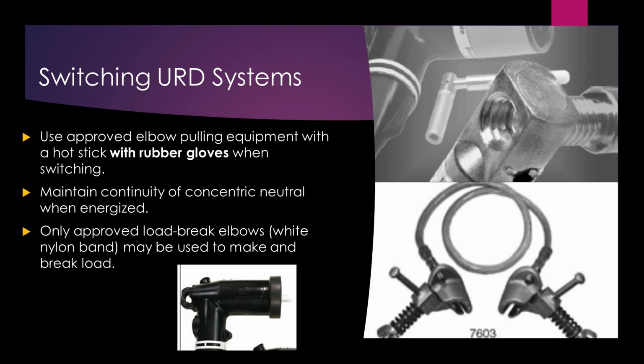It's one of those things — when electricity is flowing and doing its job, it does not want to turn loose. That's why it's so important to have approved load break elbows and load break switches, anything that can actually break that load. Once you start breaking that arc, or try to and it forms, it does what it wants. If it ionizes the air to that elbow and decides that's too far a jump, it might jump to the case ground, or to another phase, or to the X2 bushing, and it'll keep doing that until whatever equipment is backing you up actually clears it. So make sure you have an approved load break device.